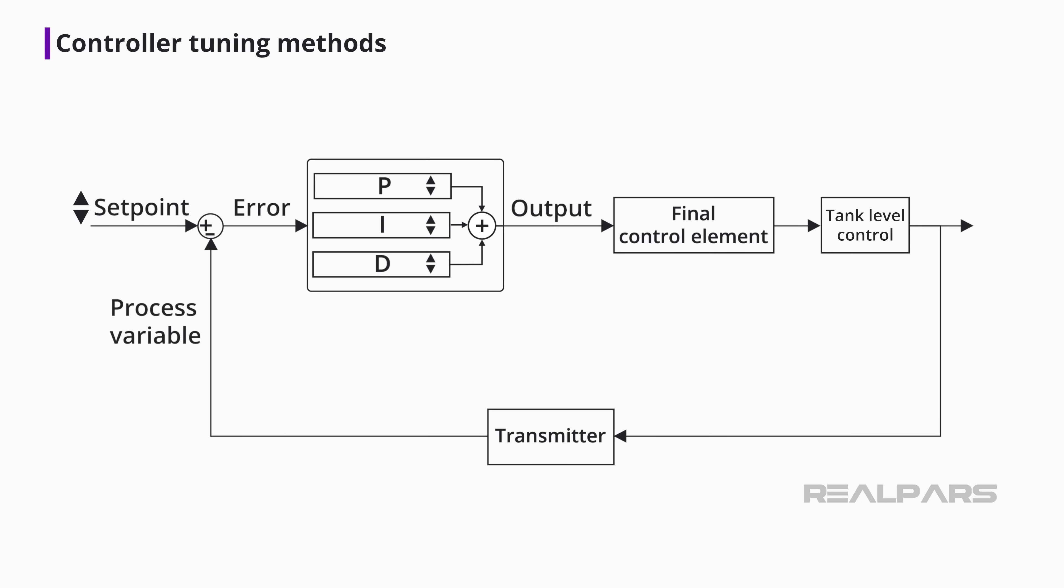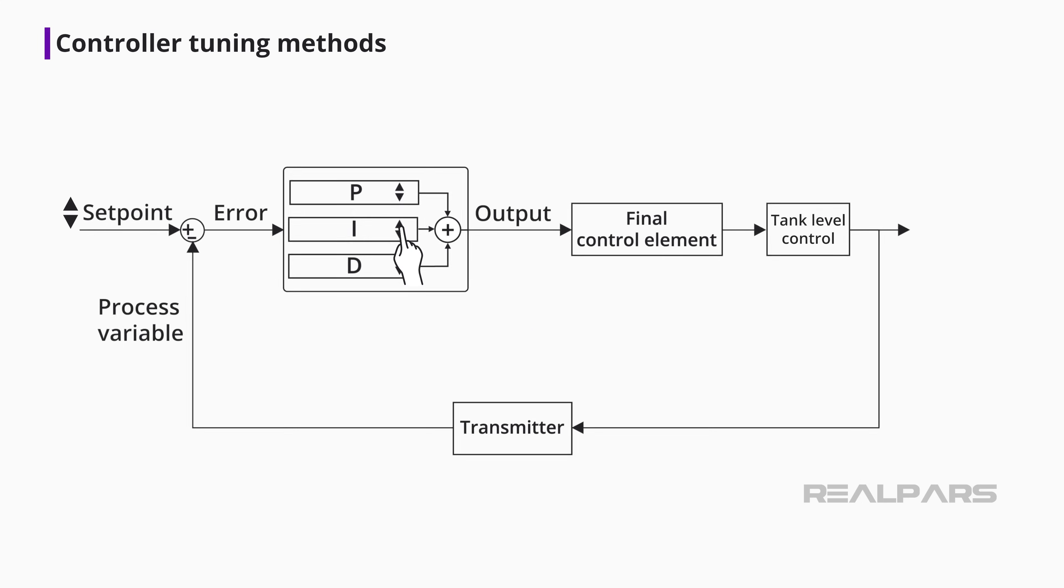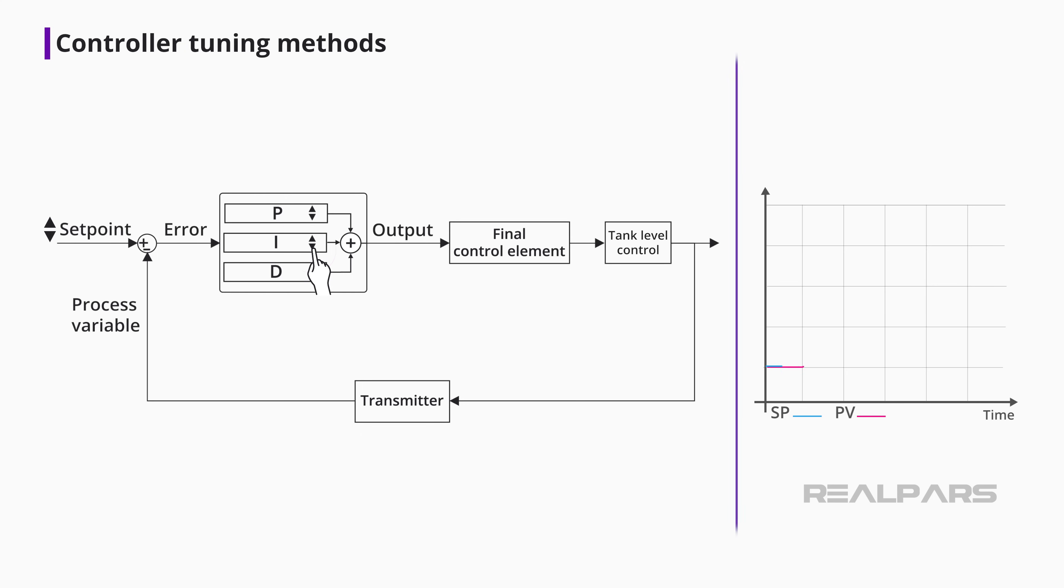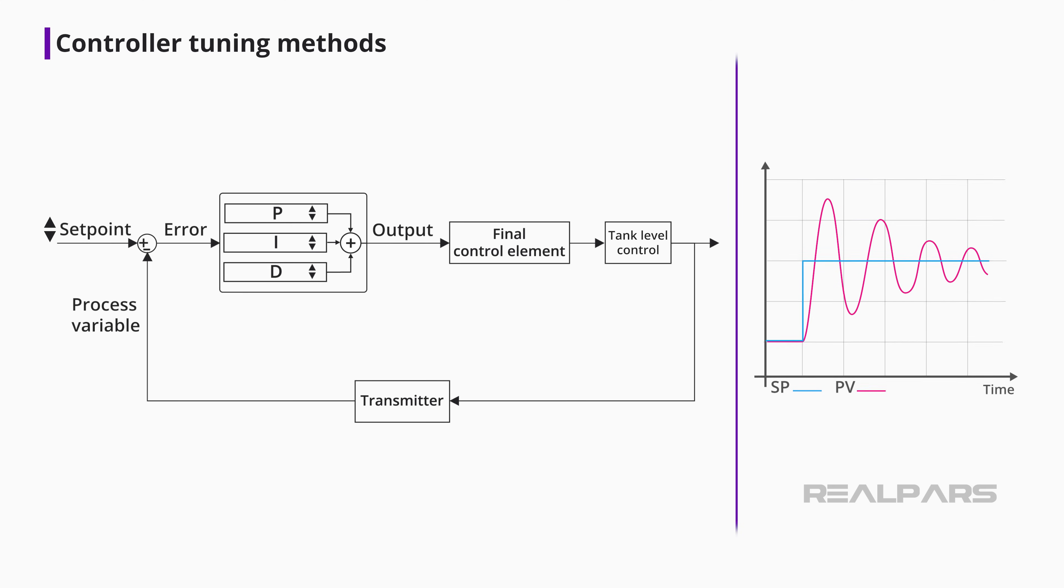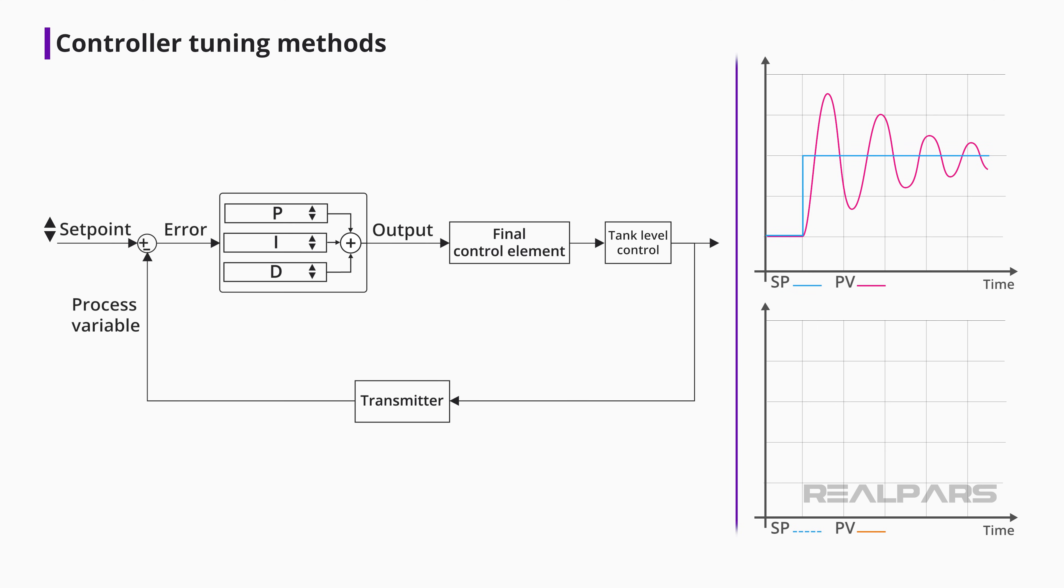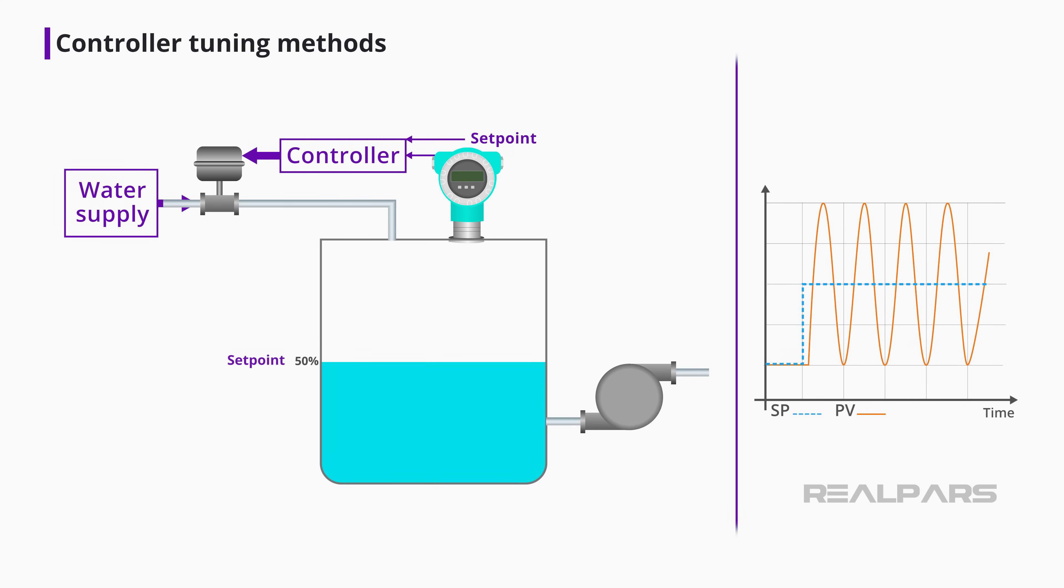There are many different manual methods for tuning a controller that involves observing the process response after inflicting controller setpoint changes. One method involves increasing the amount of setpoint change and repeating the procedure until the process enters a state of steady-state oscillation. This method of tuning produces adequate results, but is often impractical in many applications. For example, how practical is it to force the fluid level in a large tank to reach a steady-state oscillation?